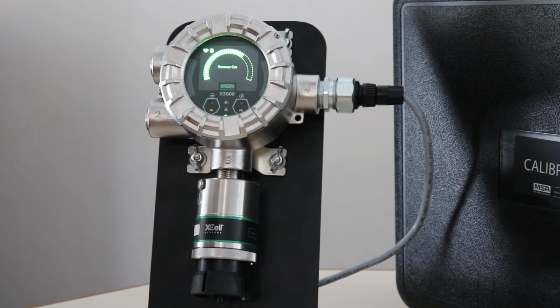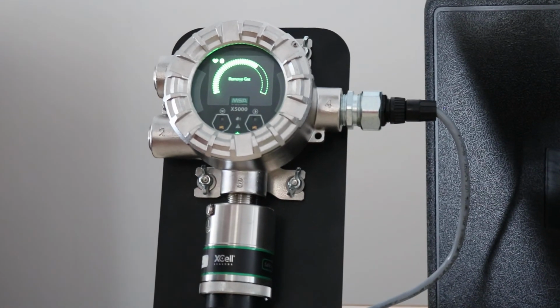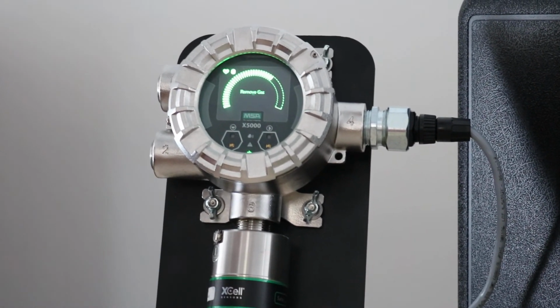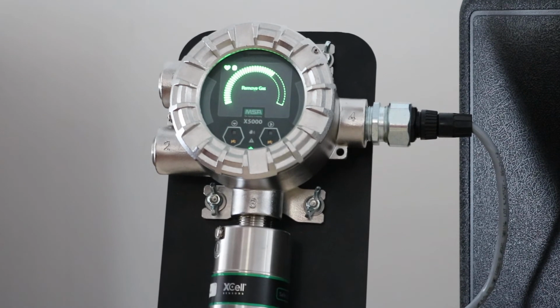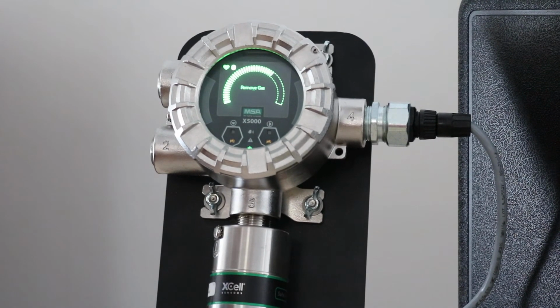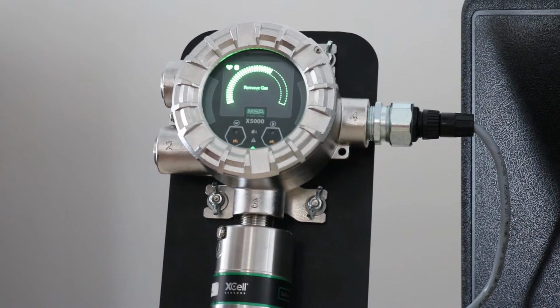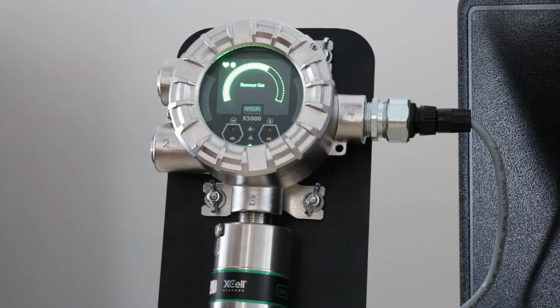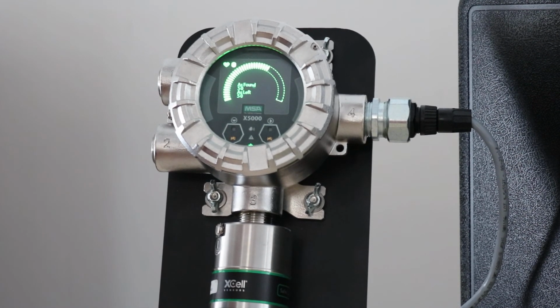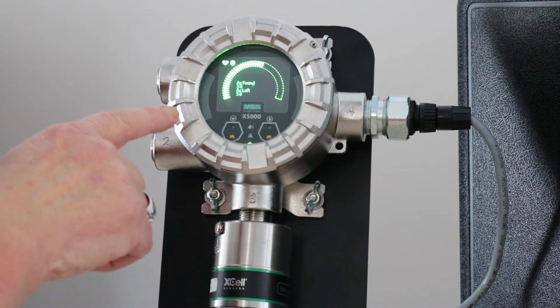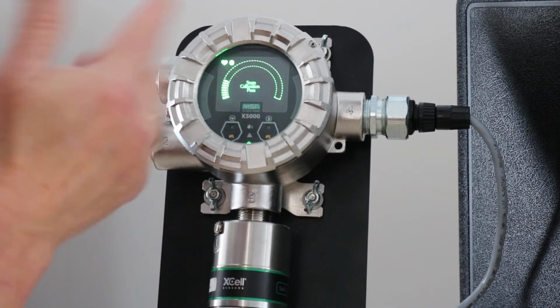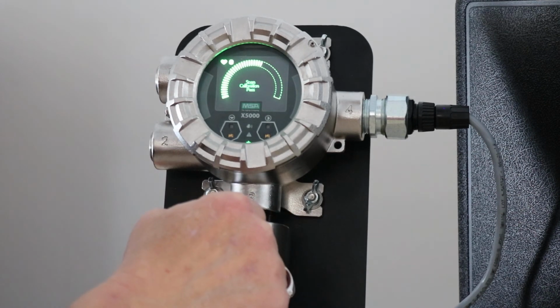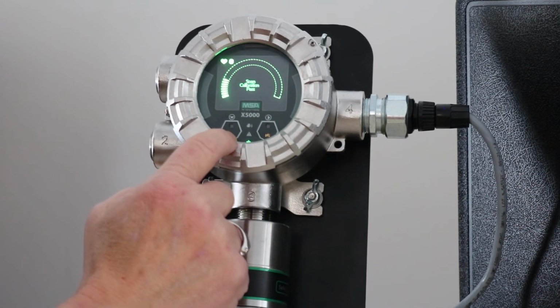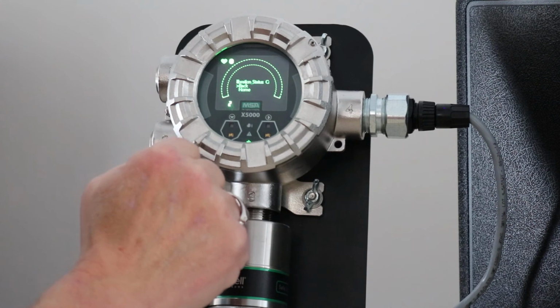And now it is going through internally and doing its calibrations. If we keep watching, we will see it come on and give us all the information that it found. Again, I don't want to edit out this time because I want you to see the length of time it does take. Okay, as found 50%, as left 50%. So it really didn't need calibration in this case. Okay, and it says calibration passed.